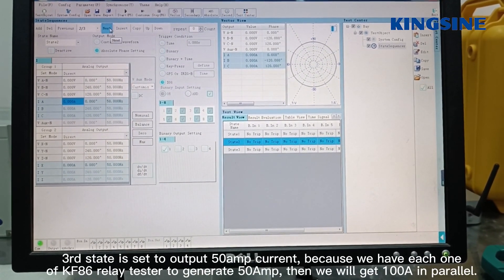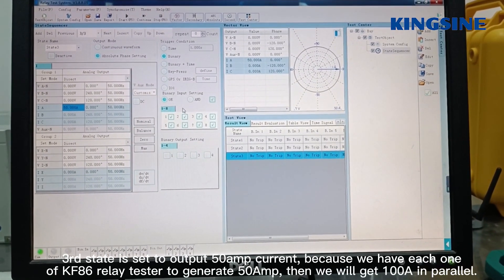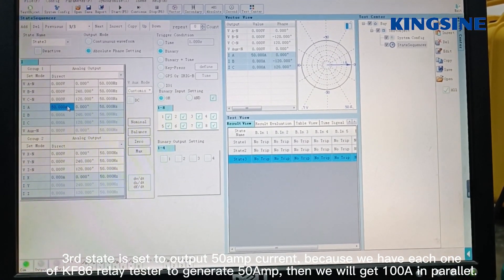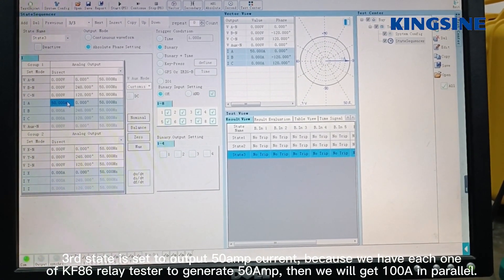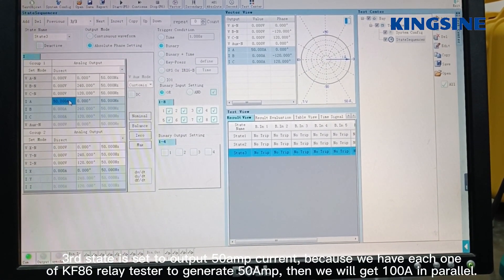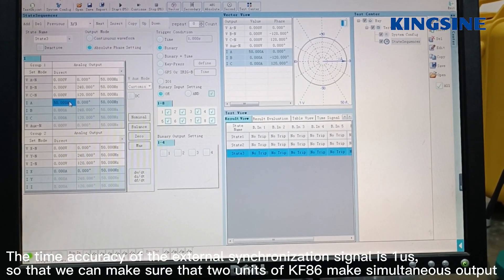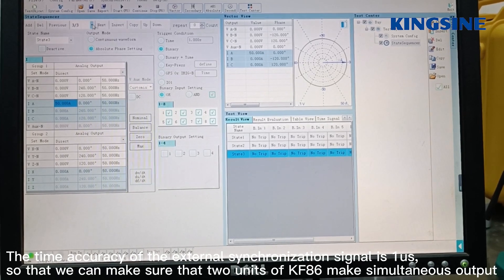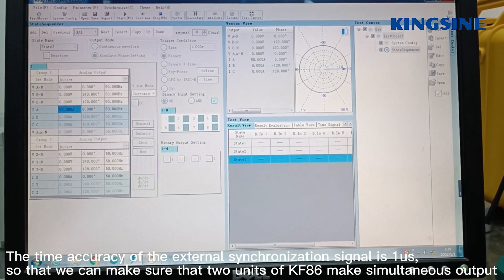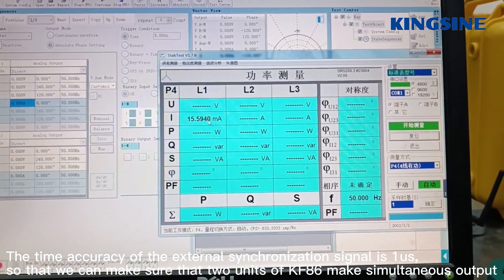The third state is set to output 50A current. Because each one of the KF86 testers will generate 50A, we will get 100A in parallel. The time accuracy of the external synchronization signal is 1 microsecond, so we can make sure that the two units of KF86 make simultaneous output.